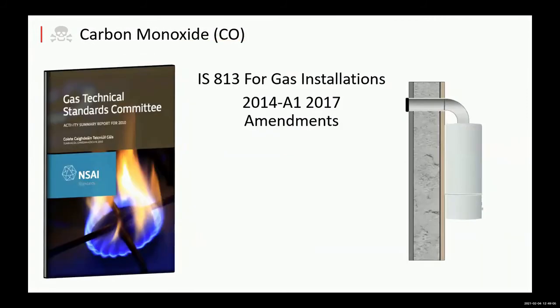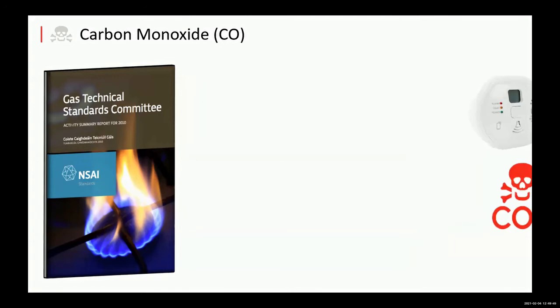Okay, for gas installations, if you look at the right-hand side of the screen, you see a gas boiler on the side. You'll see the elbow, and the bit that goes through the cavity and out on an external wall. If that is in a room on an external wall, you do not require a carbon monoxide alarm within that room unless it's a bedroom. That's from an amendment in 2017. So with just a boiler like that on an external wall, that doesn't require a carbon monoxide alarm in that room. But again, practicalities have seen that guys are putting in carbon monoxide alarms in those rooms anyway, but it's not there under the standard.